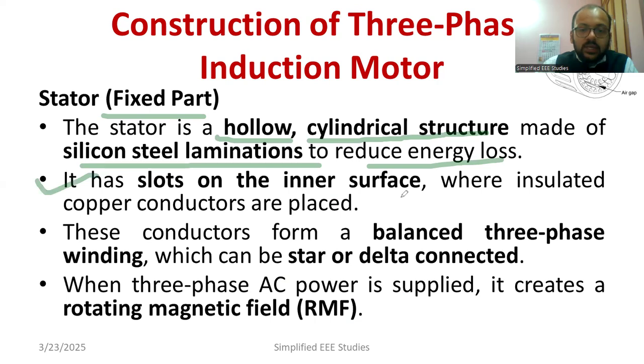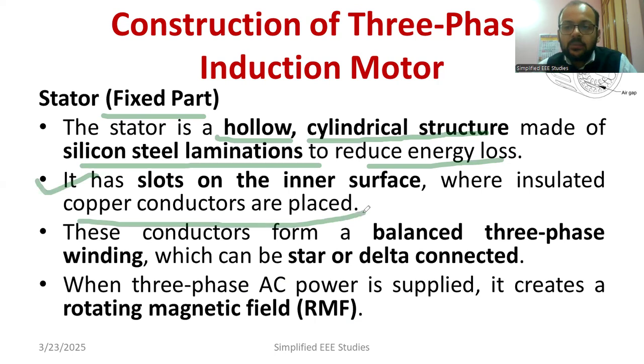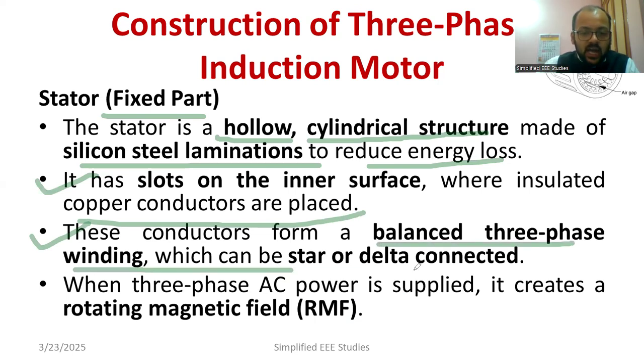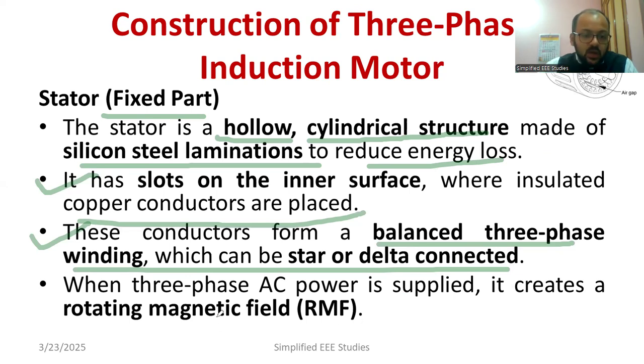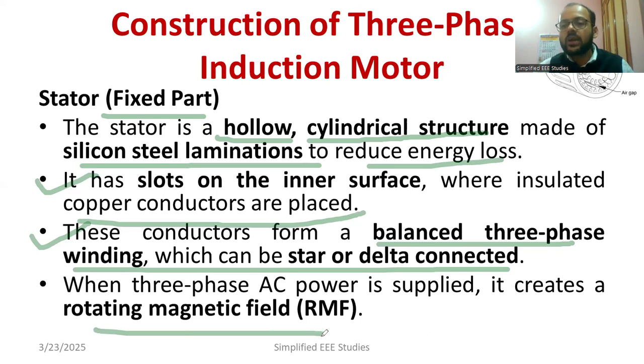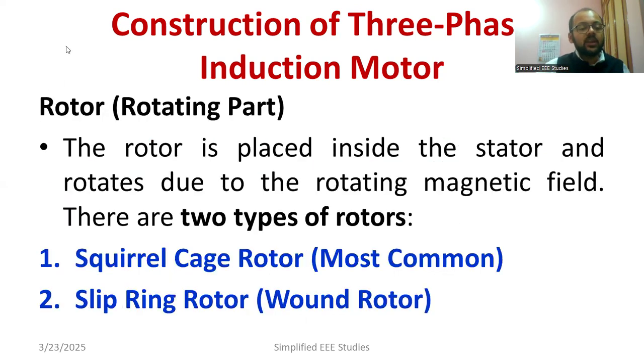The stator has slots on its inner surface, which are insulated, and copper conductors are placed in them with suitable insulation. The stator winding can be done in either a star connection or delta connection. For high voltage and low current applications, we go for star connection; for high current and low voltage, we use delta connection. A rotating magnetic field is generated as soon as supply is provided at the stator side.